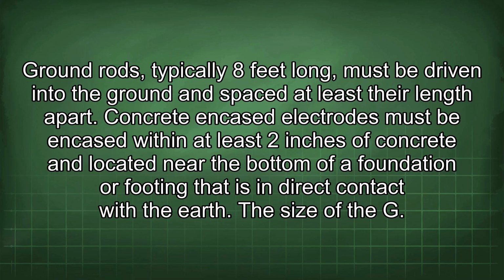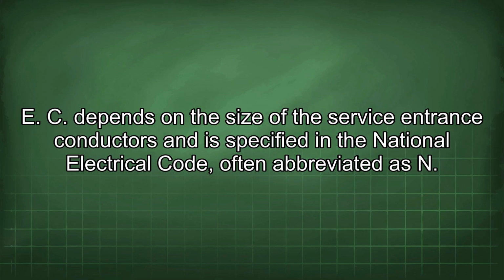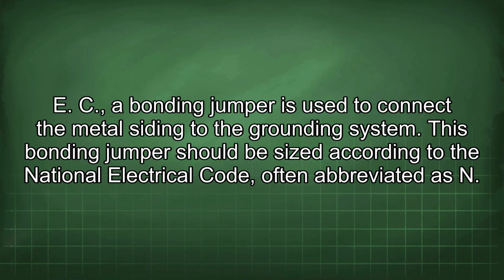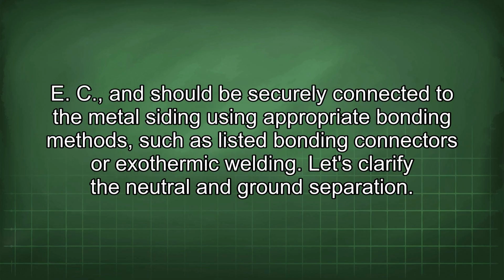The size of the GEC depends on the size of the service entrance conductors and is specified in the National Electrical Code, often abbreviated as NEC. In addition to the GEC, a bonding jumper is used to connect the metal siding to the grounding system. This bonding jumper should be sized according to the National Electrical Code, often abbreviated as NEC, and should be securely connected to the metal siding using appropriate bonding methods such as listed bonding connectors or exothermic welding.